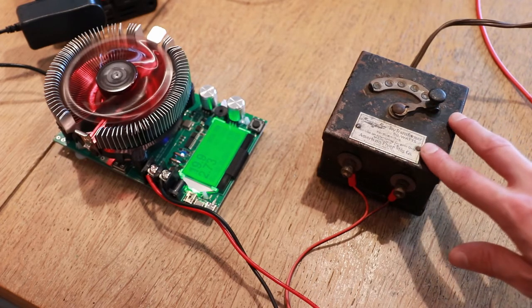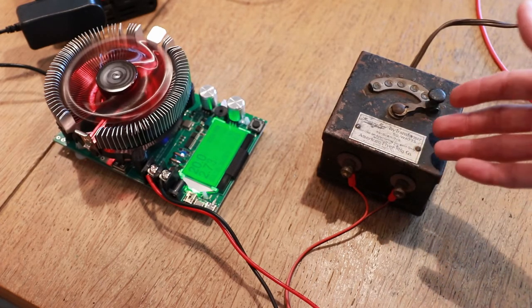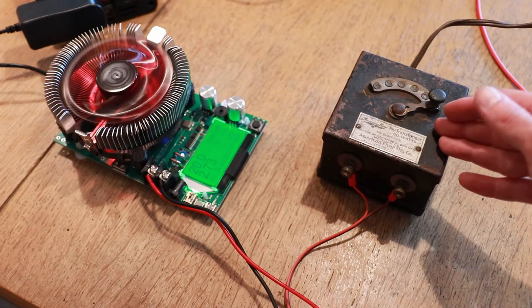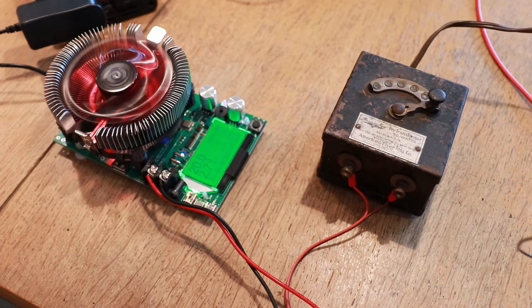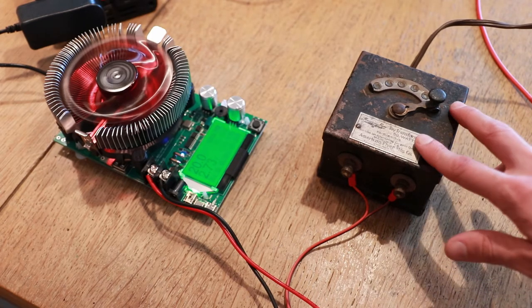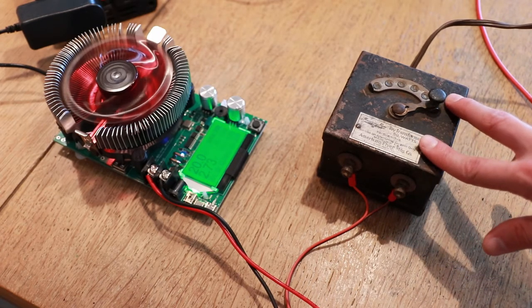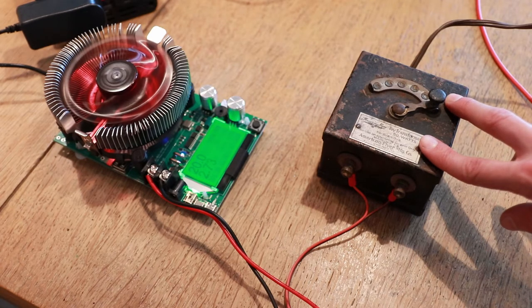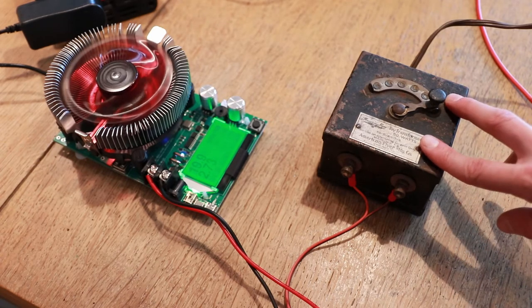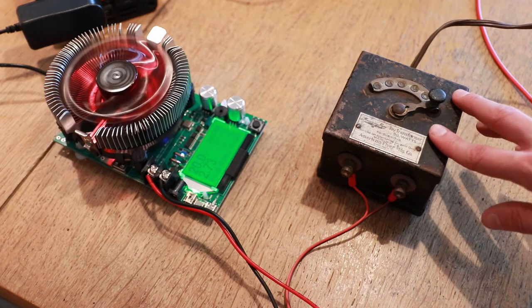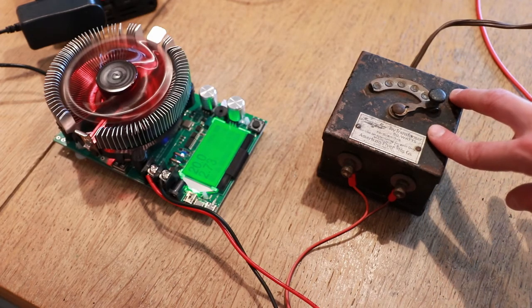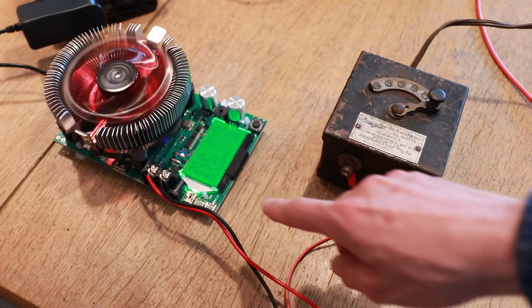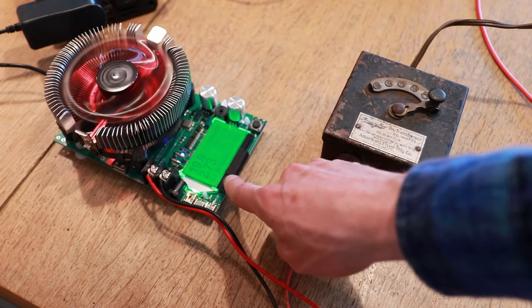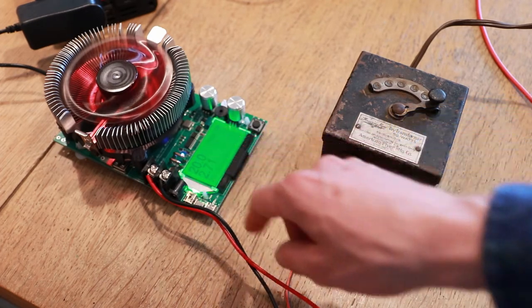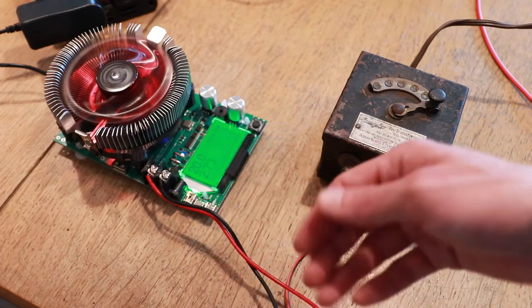By increasing the frequency to 400 Hz, available from a 400 Hz inverter module, I could afford to run much higher voltages through the transformer without driving it into saturation. So I ran this at 240 volts instead of 120, and was able to cut my current in half to get the same power output, since the output voltage is of course double.